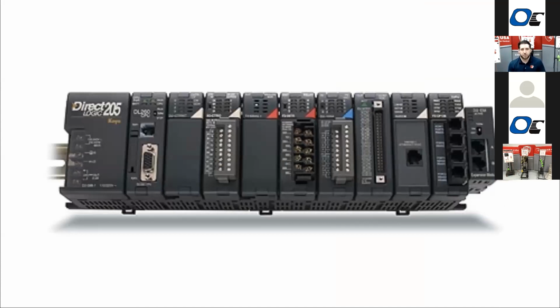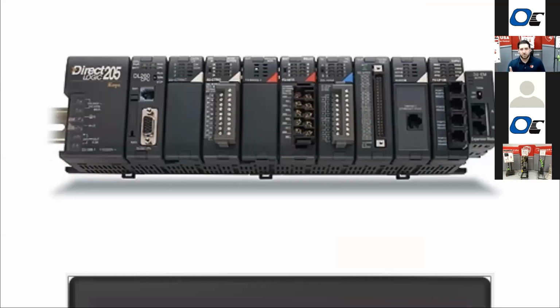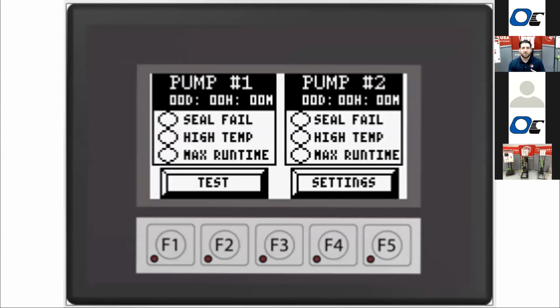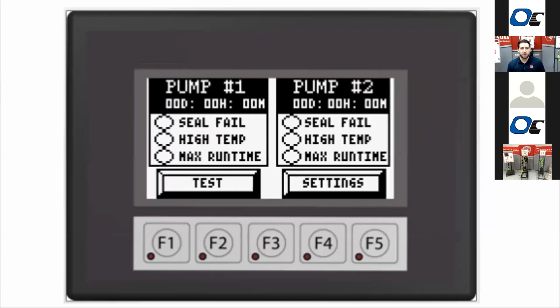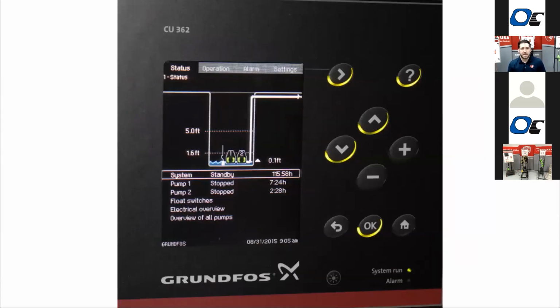So the PLC, programmable logic controller, is basically a small computer inside of the panel, and we would do the programming there specific to that application. It would be paired with a touchscreen program that would give you that HMI to be able to see what's going on with the system, make changes, things like that. So really any application where we're controlling multiple pumps or valves, we're going to recommend moving to a PLC driven panel. It just gives you a lot more flexibility. And ultimately the end result is going to be a better panel or better control when you move to that from the relay logic.